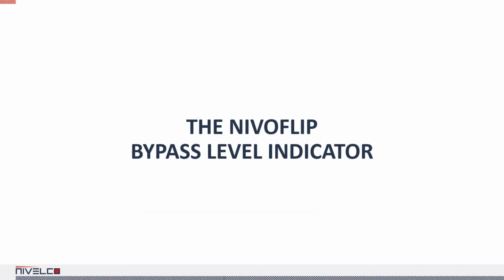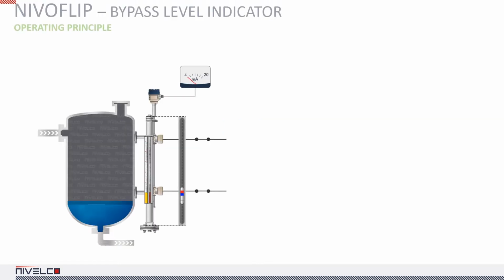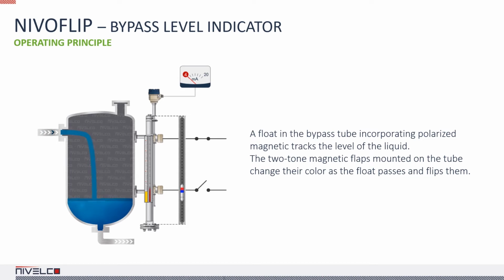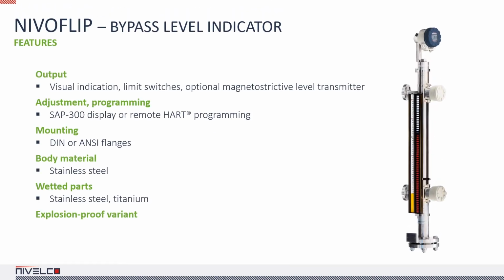The NIVOFlip is a bypass level indicator for pressurized liquid containers with a flange distance up to 18 feet. The device is PED approved, so it can withstand up to 100 bar pressure. The NIVOFlip can be equipped with optional limit switches or NIVELCO's NIVOTRAC high-precision magnetostrictive level transmitters if digital communication is necessary. High-temperature versions can withstand up to 482 degrees Fahrenheit. The magnetic float in the bypass tube tracks the level of the liquid, and the two-tone flaps change their color as the float passes and flips them. The bypass tube and the float are made of stainless steel, but a titanium float is also available for liquids of lower density.